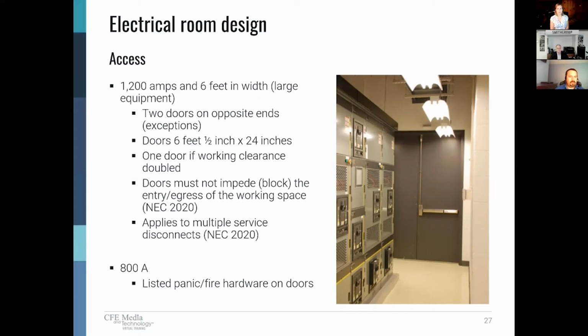consider an electrical room, access to that room, larger pieces of equipment may necessitate very specific requirements to be met. So if you've got equipment that's over 1200 amps, 6 foot in width, so this is large equipment we're talking about. This isn't a small electrical room with a couple of branch panels in it. The larger equipment requires 2 doors, one on each end, on opposite ends. There are some exceptions, and we'll get into those here in a second, but the doors need to have a certain height and a 24-inch width. And if you have double the working clearance in front of the equipment, and here's the exception, then you can get by with one door.